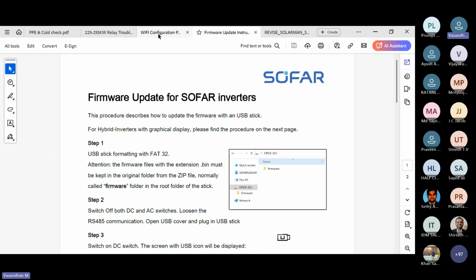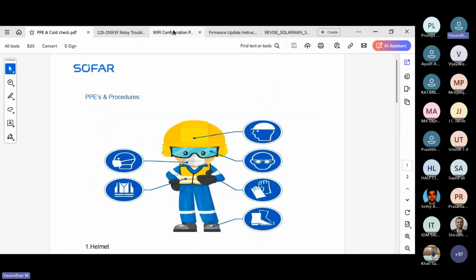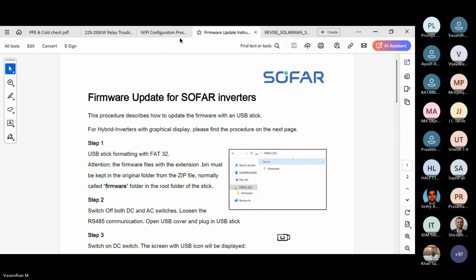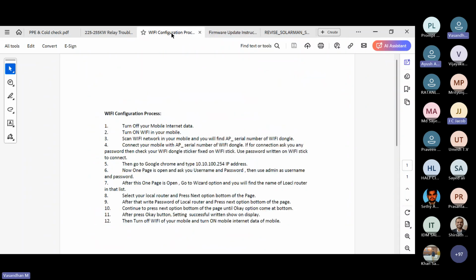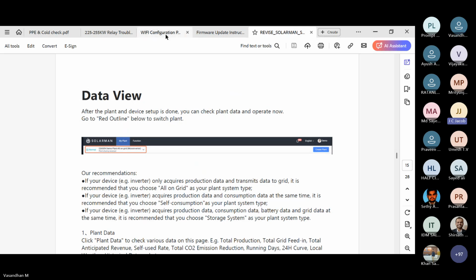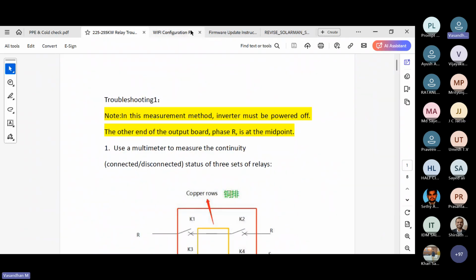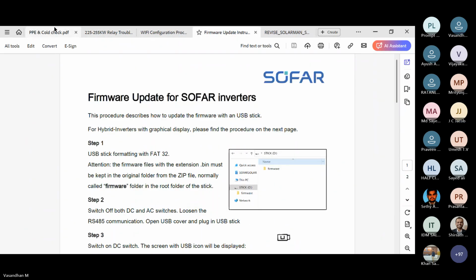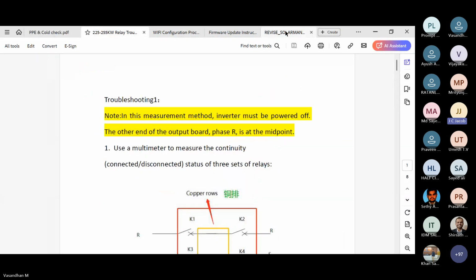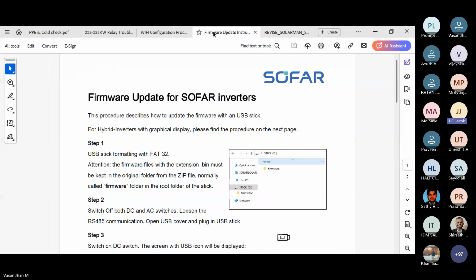Sir, default range is based on your grid standard, right? How much you are getting from the grid line, like sometimes 240, sometimes 260, sometimes 250. It's based on your grid standard. So minimum rated voltage is 230, and it will adjust based on that. At any point of time, the inverter output will be 5 to 10 volts more than the grid voltage, right? Yes, it will always be plus only, because you have to push power from your inverter.